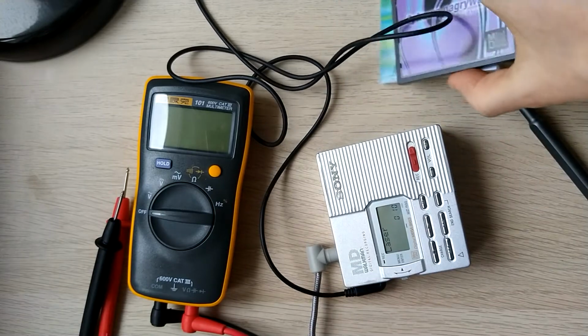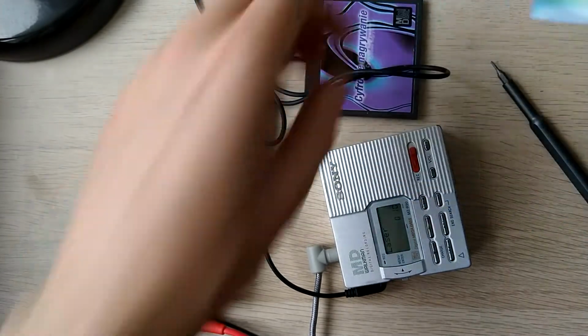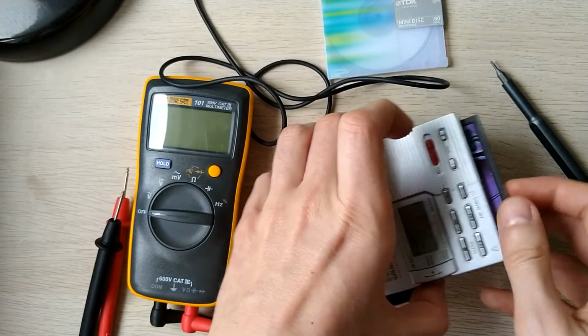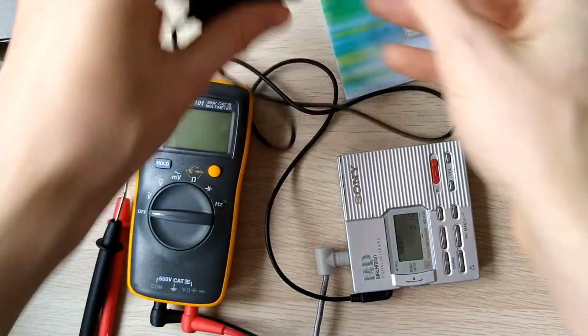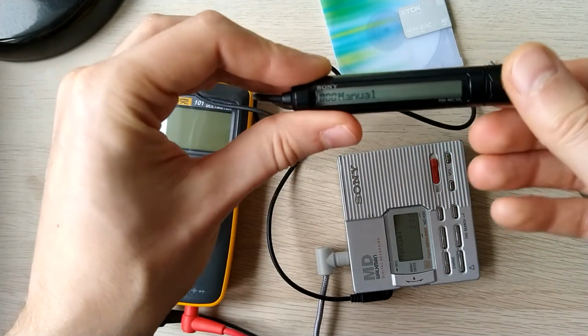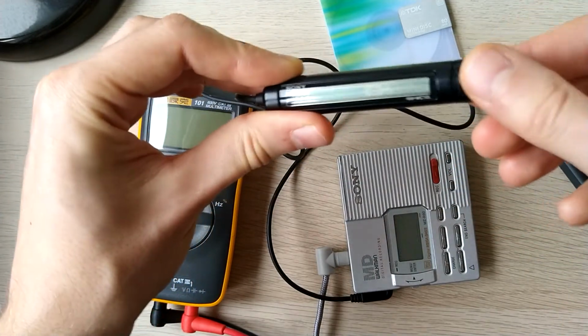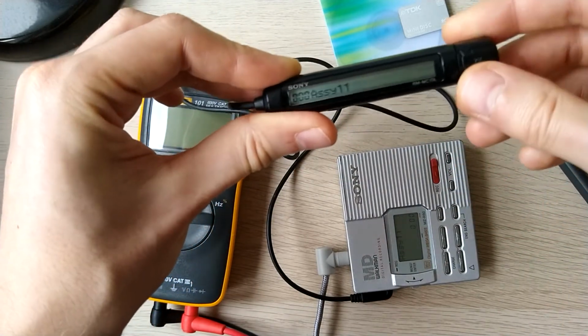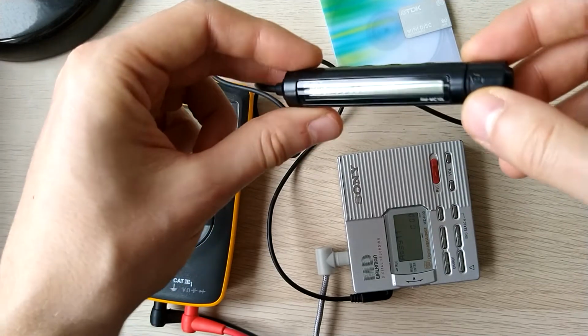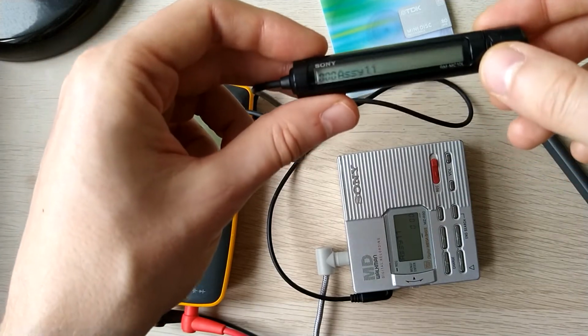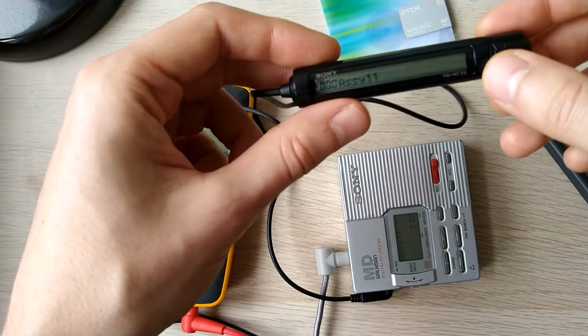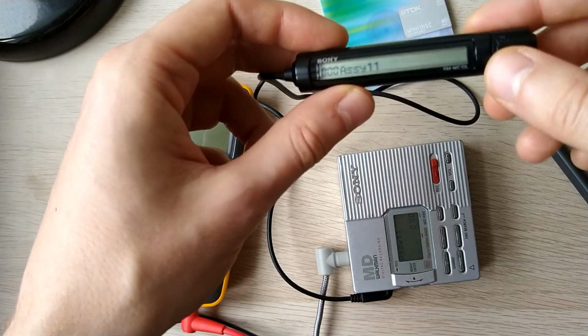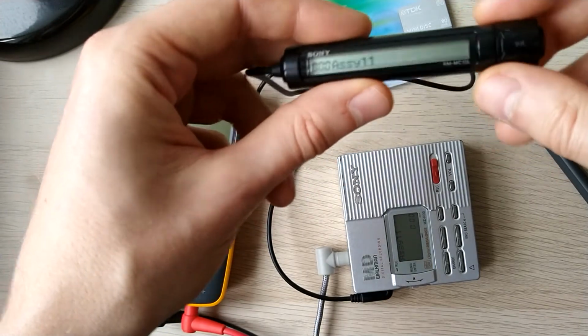So for that we need to begin with a pre-recorded MD. And using the service menu, we press the backward button, and it says ASSY11. 11 means that the adjustment has not been done yet. Until this clears, the device will refuse to start normally.